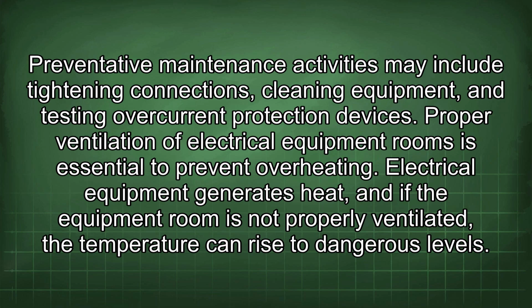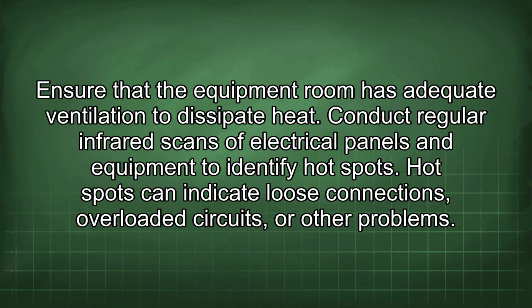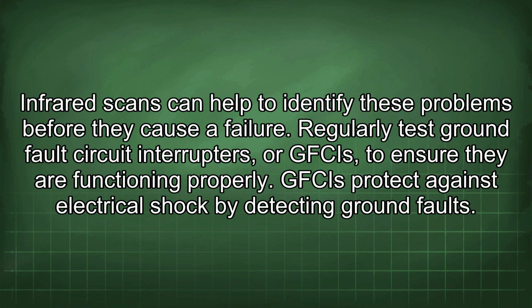Proper ventilation of electrical equipment rooms is essential to prevent overheating. Electrical equipment generates heat, and if the equipment room is not properly ventilated, the temperature can rise to dangerous levels. Ensure that the equipment room has adequate ventilation to dissipate heat. Conduct regular infrared scans of electrical panels and equipment to identify hotspots. Hotspots can indicate loose connections, overloaded circuits, or other problems. Infrared scans can help to identify these problems before they cause a failure.